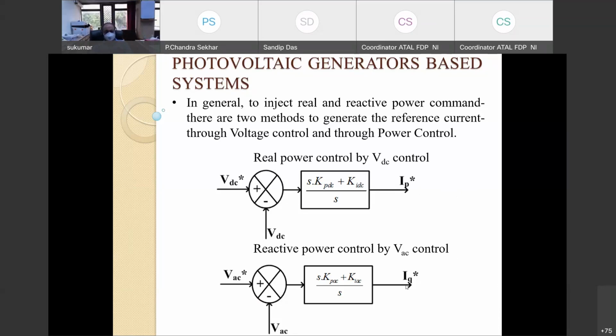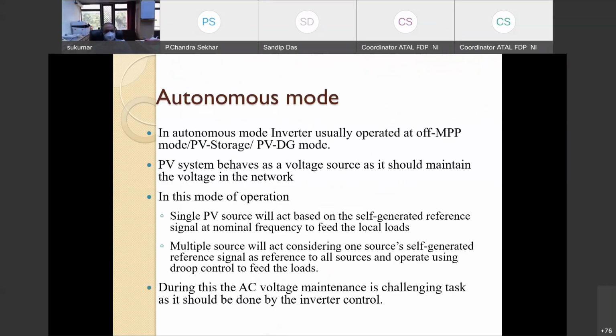And the reactive part of the inverter current is generally done with respect to the voltage, but in general, this PI controller is not used. We use a simple proportional control so that we can have the droop philosophy put into its operation, because it is very difficult to go for grid voltage control using reactive power control, because the grid is a very big system as compared to the inverter being used. As I have already mentioned, the autonomous mode can also have MPPT operation, and the droop can be added to it for multiple operation.